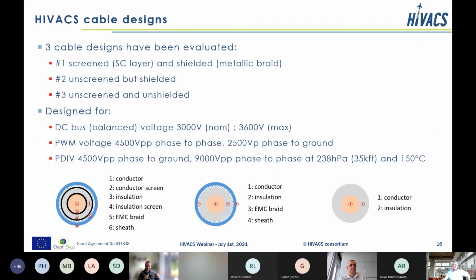Then for the HIVACS project, in addition to all those model cables, gauge 12 and gauge 0, we have also designed 3 cables and manufactured them. There is a screened cable, design number 1, with the semiconductive layer; an unscreened cable but shielded, so it still has an EMI braid around the insulation; and a third one without any screen or EMI braid. Those cables had been designed for a DC bus voltage of 3000 volts and for a PDIV, partial discharge inception voltage, phase to ground of 4500 volts peak and phase to phase of 9000 volts peak at a pressure of 238 hectopascals or 35 kFeet.